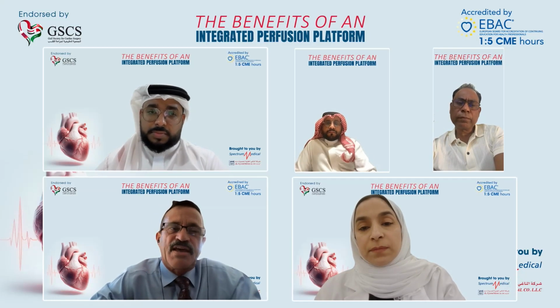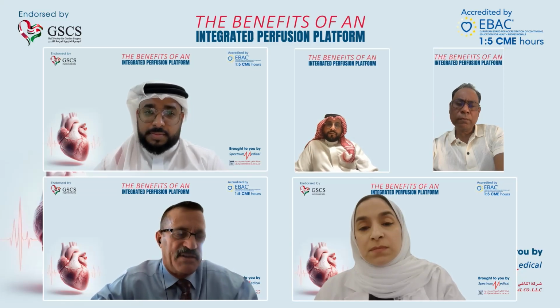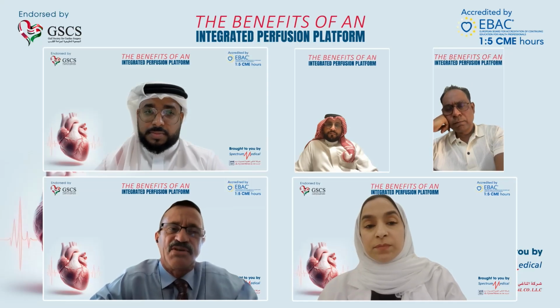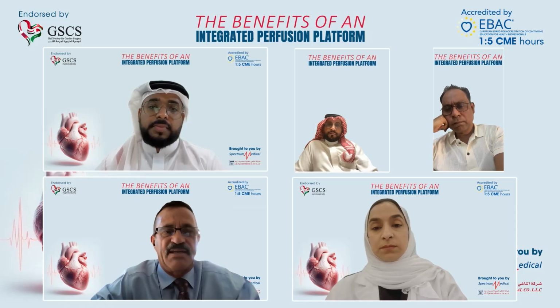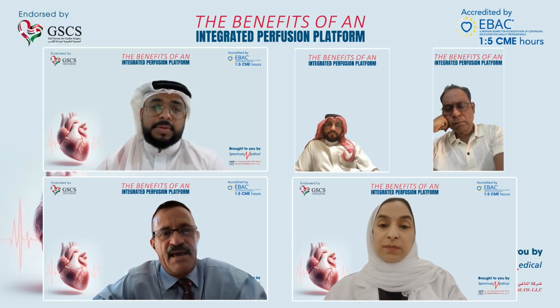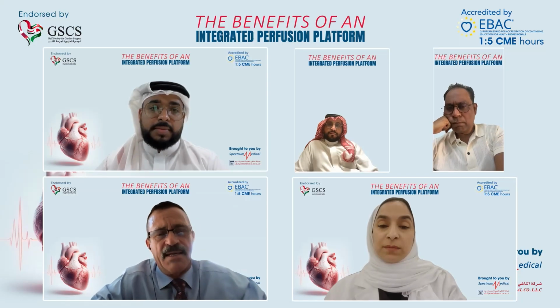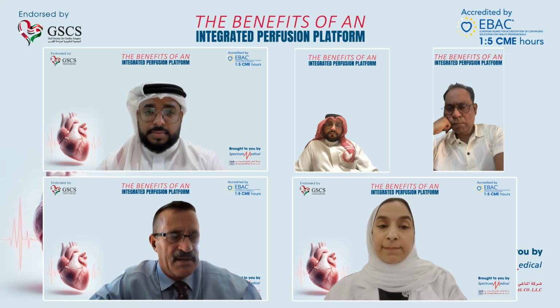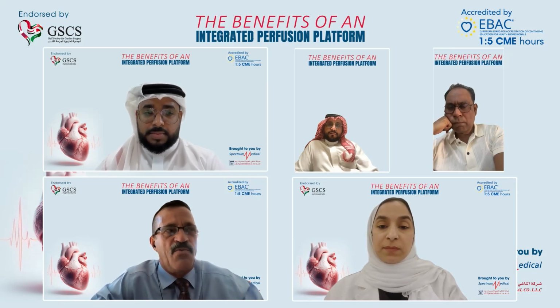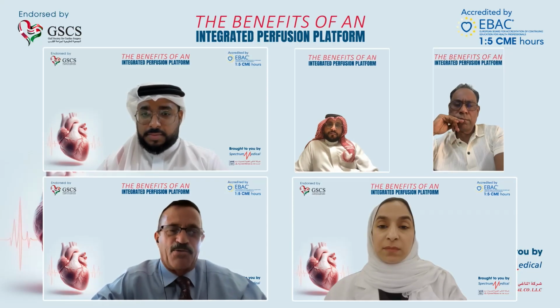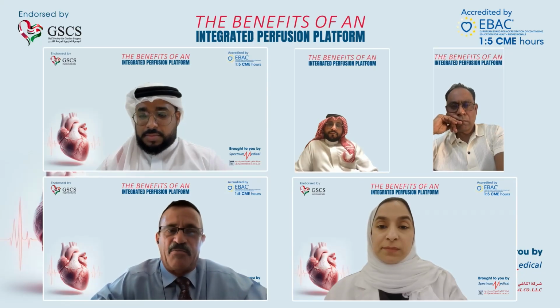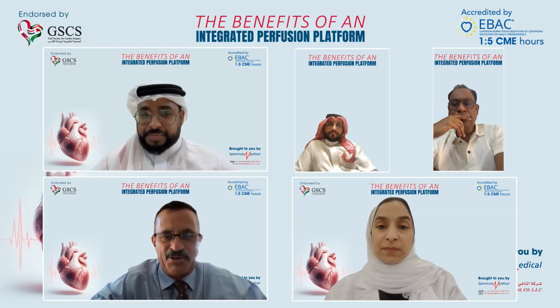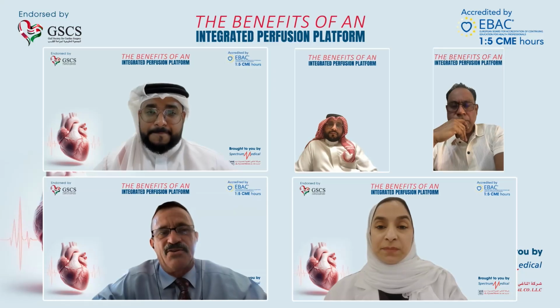So I think the first thing regarding accuracy, because of the type of technology that Spectrum uses to determine those values, is that it's really important that you get a good initial calibration. And that's something else that is, I think, unique. The way I practice that is I go through my auto initiation mode, get everything stable, and then at that point get my initial calibration. So I'm not changing temperature. I'm not doing any other adjustments to the bypass until I get that initial calibration.